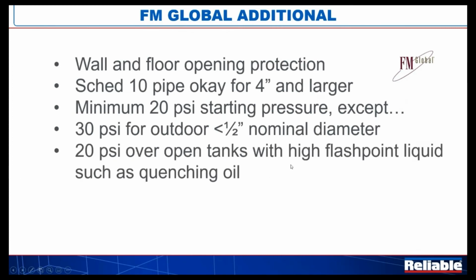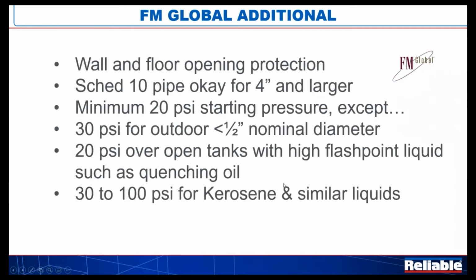20 PSI over open tanks with high flash point liquid, such as a quenching oil. Quenching is interesting as you're looking through this. If you're not familiar with it, you form a piece of metal. It's red hot. You would think dipping it in oil would be the last thing that you want to do. But quenching oil is put in a tank. It's heated, and what we're trying to do is slowly cool the piece of metal. This is used in hardening efforts to make the materials hard. So for gears, truck gears and things like that, they use quenching oil, and they control how fast or how slow that piece of material cools down, and that all aids in the hardening.